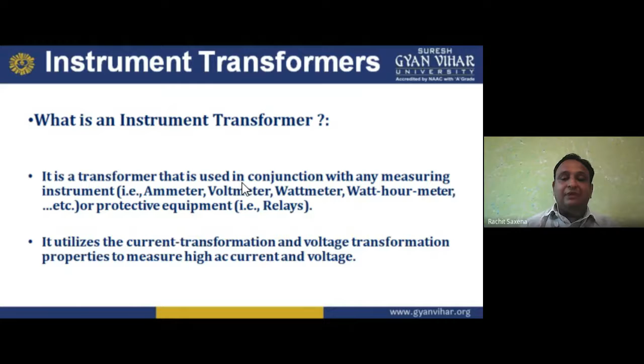For measurement of high AC current, it is usual to use a low range AC ammeter with a suitable shunt, because we have to connect it in parallel. So with a suitable shunt, we can connect a low range ammeter. For measurement of high AC voltage, low range AC voltmeters are used with a high resistance connected in series. And for the ammeter, we have the shunt resistance with a low range ammeter.